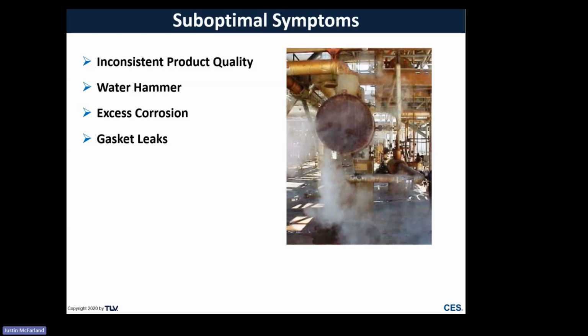Things like gasket leaks are usually a big visual indicator that something's happening, whether thermal stresses or water hammer or something like that. But gasket leaks should not be occurring. And if you see that, then it's probably something that needs to be investigated.